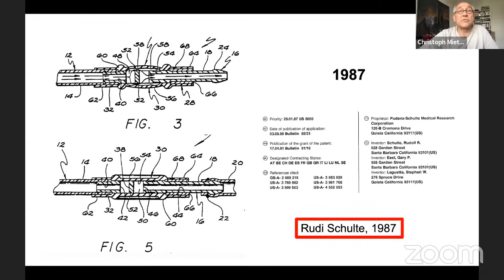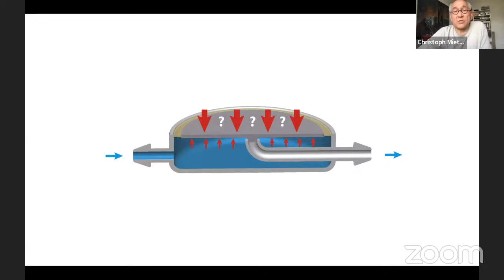A scheme is shown here: you have an inlet and an outlet, and there is no direct connection between them. The proximal pressure from the ventricles, which might increase, acts on a large area, while the closed outlet has only a small area, closed by this ball. The other force to consider is the pressure outside this device, which is often not mentioned, or seldom mentioned.